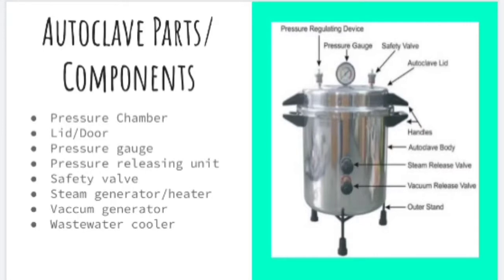The autoclaves used in healthcare laboratories have an outer jacket that is filled with steam to reduce the time taken to reach the sterilization temperature. The inner chamber is the case where the material is to be sterilized or put. The size of the pressure chamber ranges from 100 to 3000.